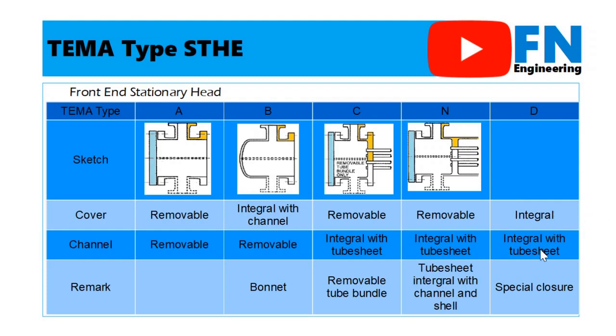The difference between type C and type N is in the tubesheet. The tubesheet in type C is only integrated with the channel, but in type N, the tubesheet is integrated with both channel and shell. So, the tube bundle using type C can be removable from the shell. The last type is type D. Type D is a special closure. It is commonly used for high pressure services. So, the cover and channel are integrated with each other and the shell.